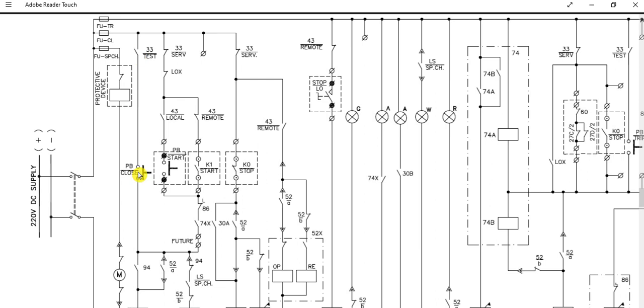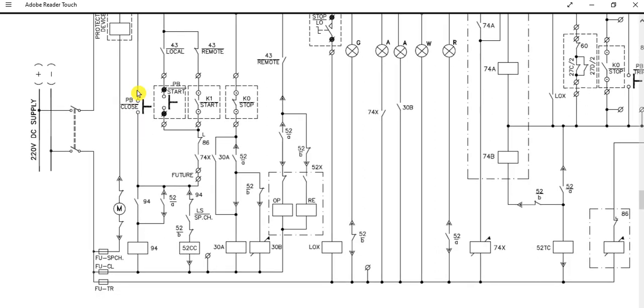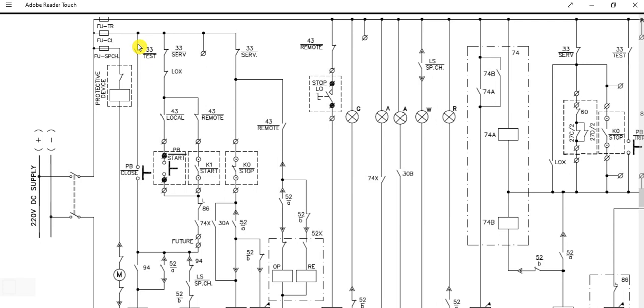In test position, if you press the push button for local operation, this path is followed. The other path is open so it will not be taken. This is the limit switch for spring charge — if the spring charging motor is charged, this contact will be closed and it will energize the 52CC closing coil of the circuit breaker, and the breaker will be closed.